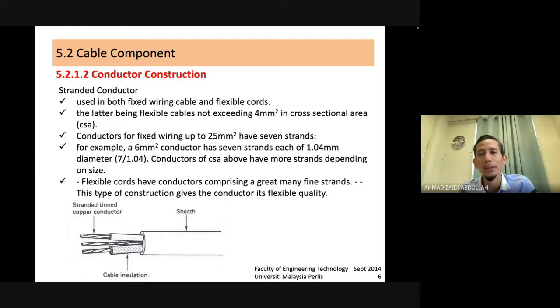But if you look in the shops, they don't follow this 7 strand. They also sell with only 3 strand. Actually, you can try: go to the shop and check how many strand there are. That's how the factory plays to get a cheap price. For example, a 6 mm conductor has 7 strand each. Conductors of larger sizes have more strand depending on size. A flexible cord has a conductor comprising a great many fine strands, and this gives the conductor its flexible quality. So this is the insulation, this is the stranded conductor, and this is the sheath.